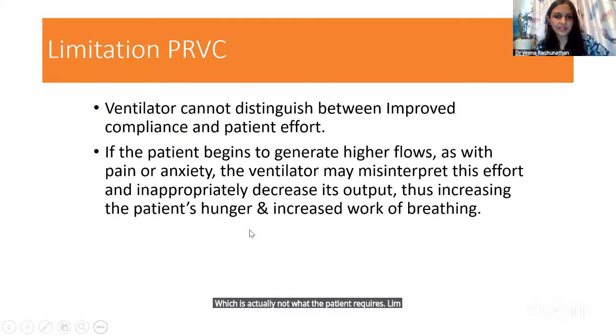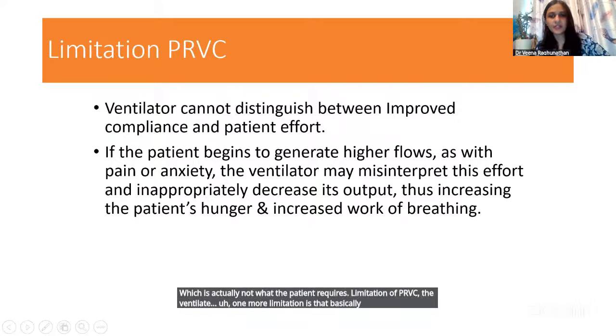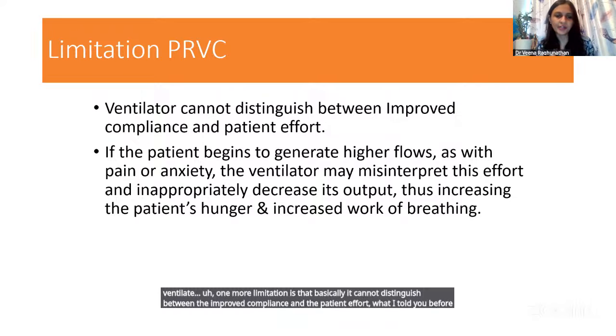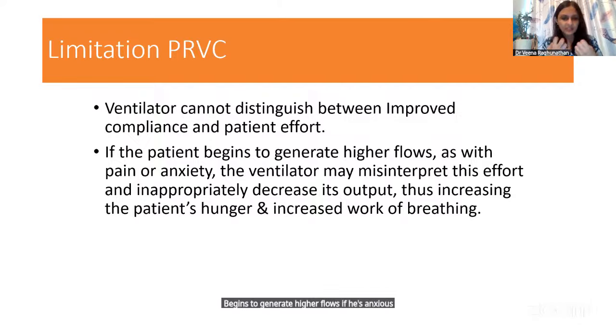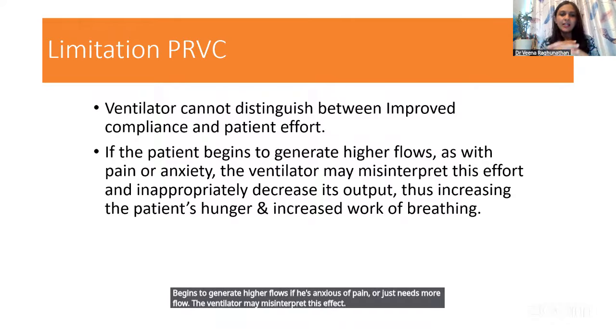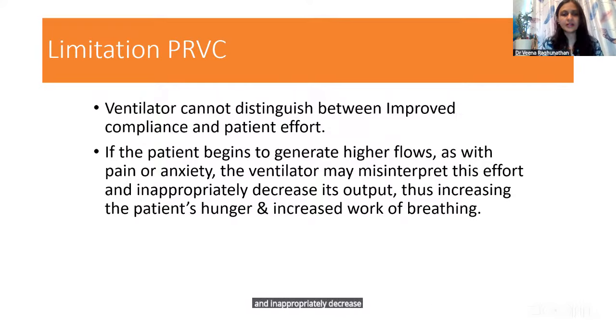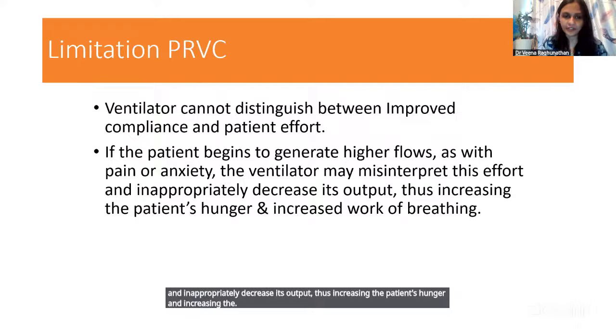Limitation of PRVC: one more limitation is that basically it cannot distinguish between improved compliance and patient effort, what I told you before. So if the patient begins to generate higher flows, if he's anxious or in pain or just needs more flow, the ventilator may misinterpret this effort and inappropriately decrease its output, thus increasing the patient's air hunger and increasing the work of breathing for the patient.